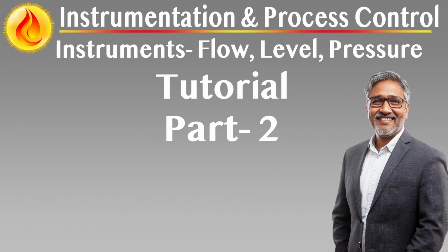Strategic instrument location for functional accuracy and field maintainability. Instrument placement must serve dual objectives: accurate representative measurement and safe, efficient access for operation and maintenance. Location is not arbitrary. It must reflect process conditions, mechanical constraints, and human interaction. For online instruments, such as pressure, level, and flow transmitters connected via impulse lines or tappings, placement must be near the process takeoff point to minimize impulse line length and response lag, free from heat, vibration, and obstruction. Position for clean, direct routing of tubing without sharp bends or unsupported runs.